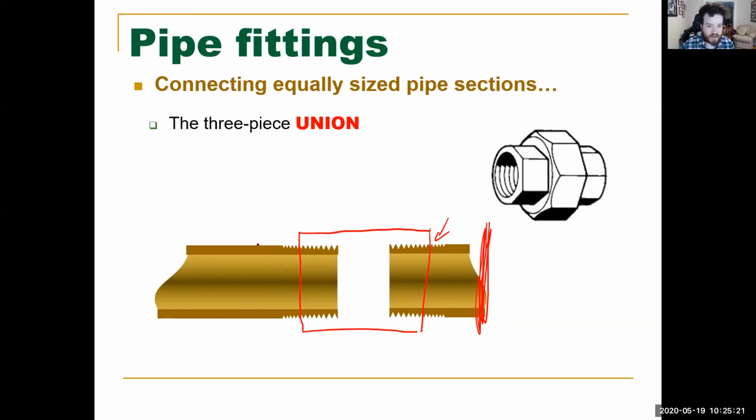And then you try and take on and screw on this side as well. Remember, this is a piece of pipe that cannot be removed. So this side's attached to a pump. What you would do is while you're tightening the pump side, the side that's attached to the wall would unthread itself. All right, so you're in a spot where you have two pieces of pipe that cannot be connected, because if you try and connect one side, it's unthreading the other. So that's where a union comes in.